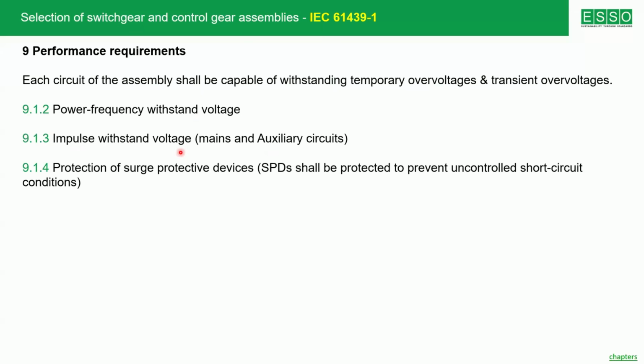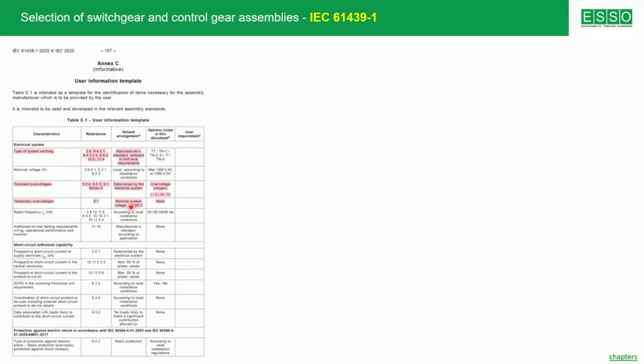Impulse withstand voltage means how much voltage the equipment is able to withstand during a switching action. Protection of surge protective device is also something related to earthing. The most important point is that SPDs shall be protected to prevent an uncontrolled short circuit condition. The SPDs may fail at the end of life. We say at the end of life of the SPD, it will create a short circuit, and the entire SPD along with its protective device, backup protection, must be capable of preventing an uncontrolled short circuit condition. That means you are supposed to use an SPD with an integrated backup fuse, which is the best way. Now, in the standard 61439 Part 1, there is an Annex C, user information template.